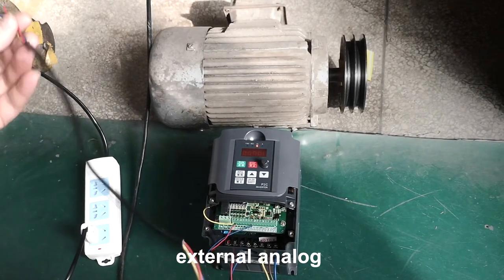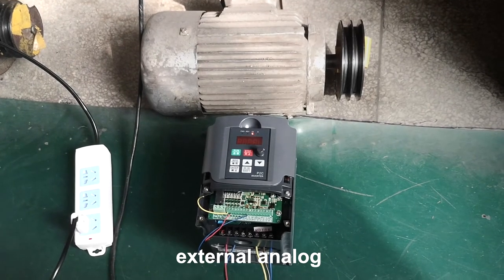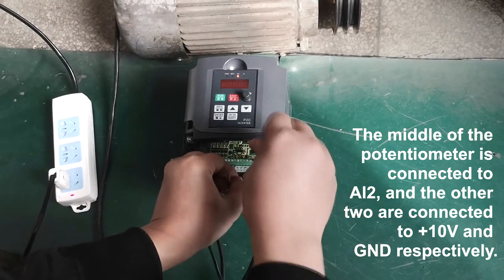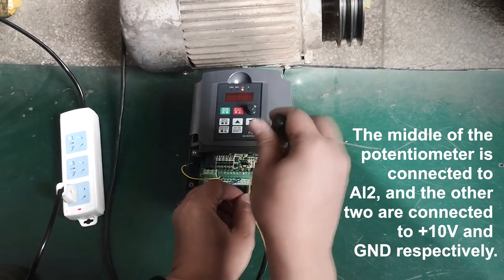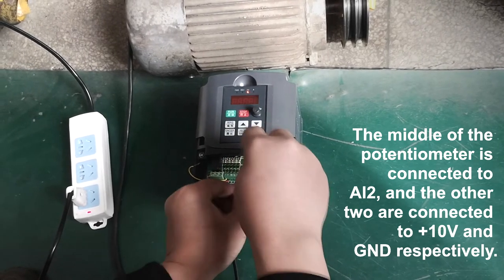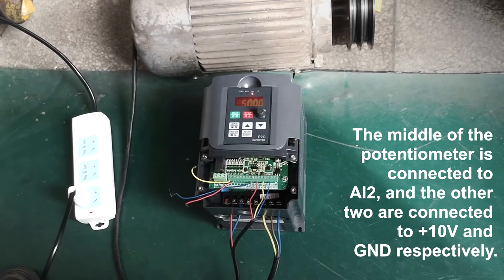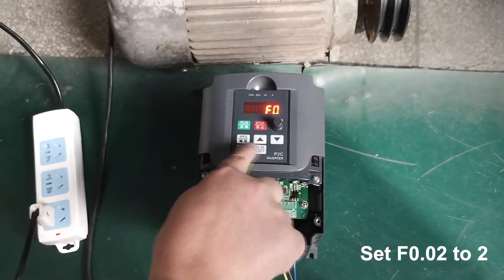External analog: the middle of the potentiometer is connected to AI2, and the other two are connected to PLUS10V and GND respectively. Set F0.02 to 2.